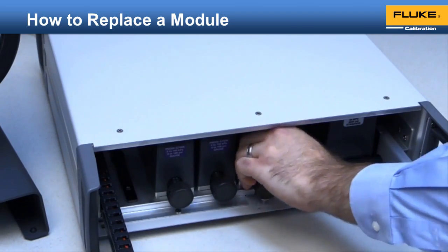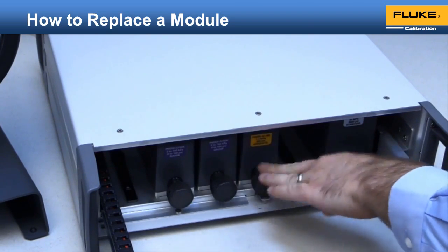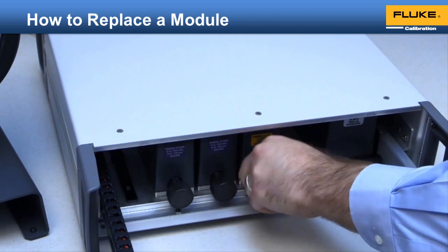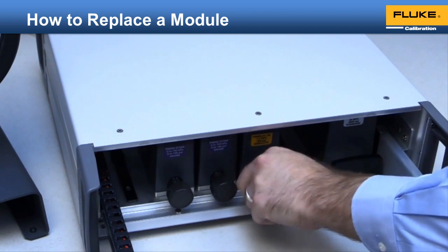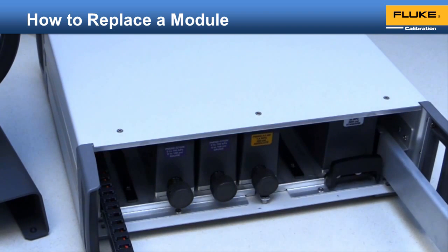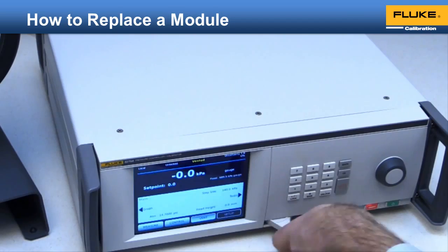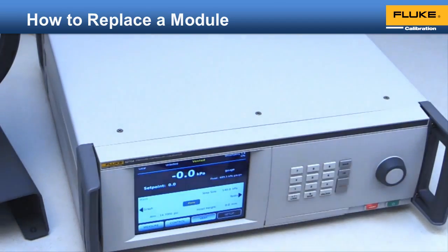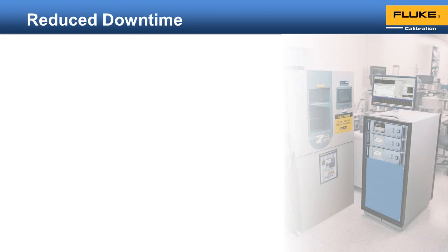Fasten the module into place by tightening the knob until it clicks. The knob is torque limiting. Once it clicks, you know the O-rings have been sufficiently compressed. The module will be automatically recognized and appear on the 6270A's main screen. Then just close the door and start using the 6270A to control pressure again. The third main benefit of a modular system is reduced downtime.